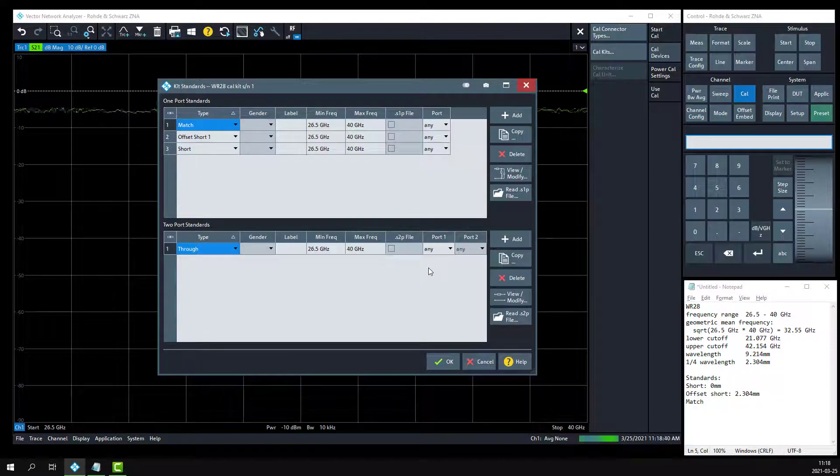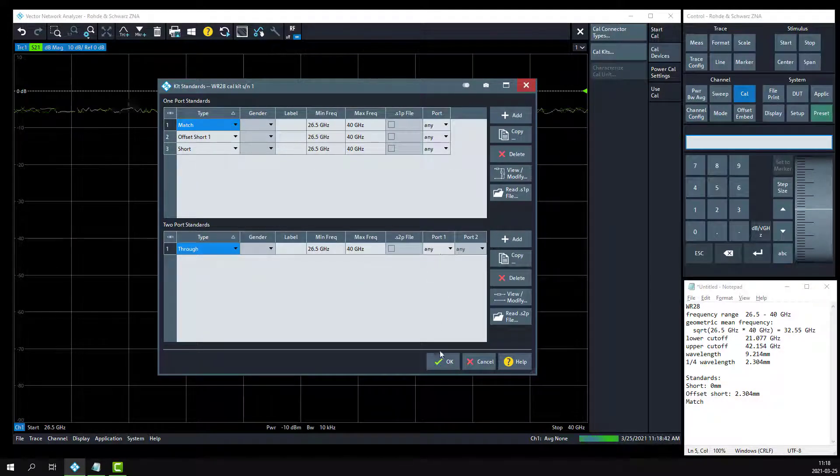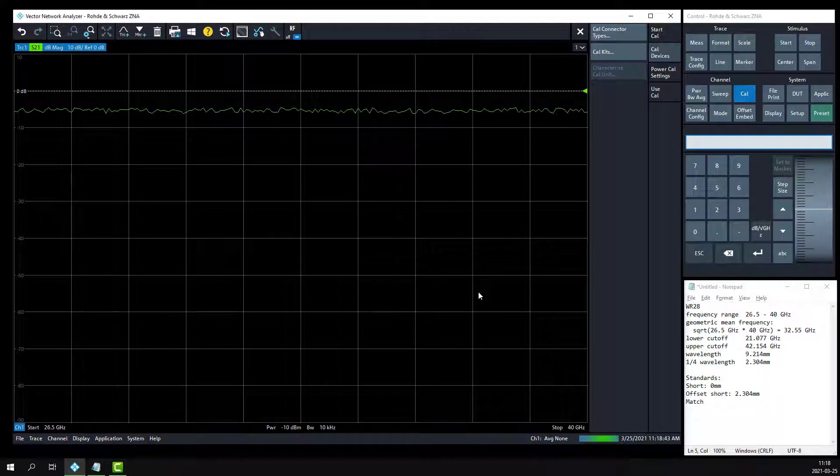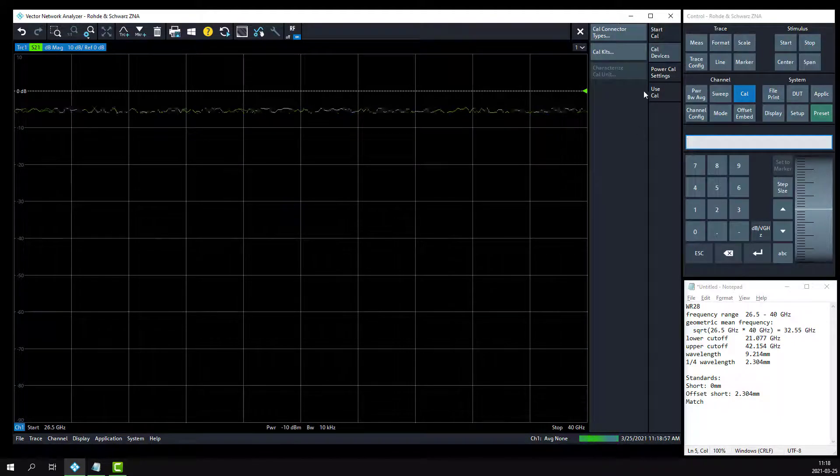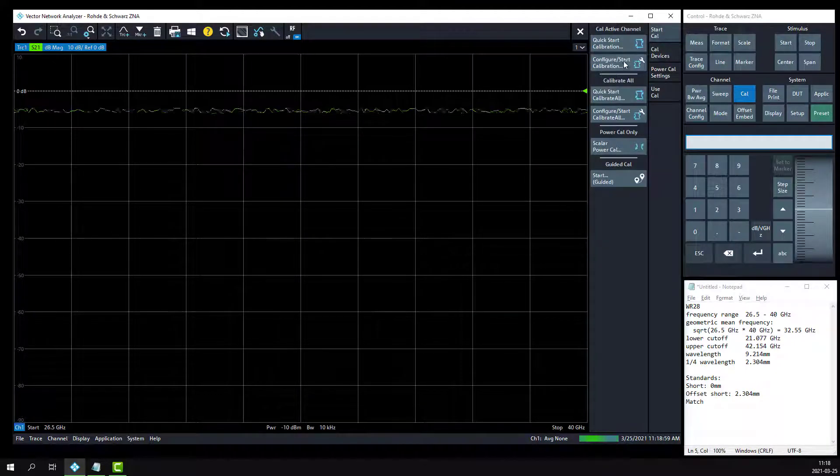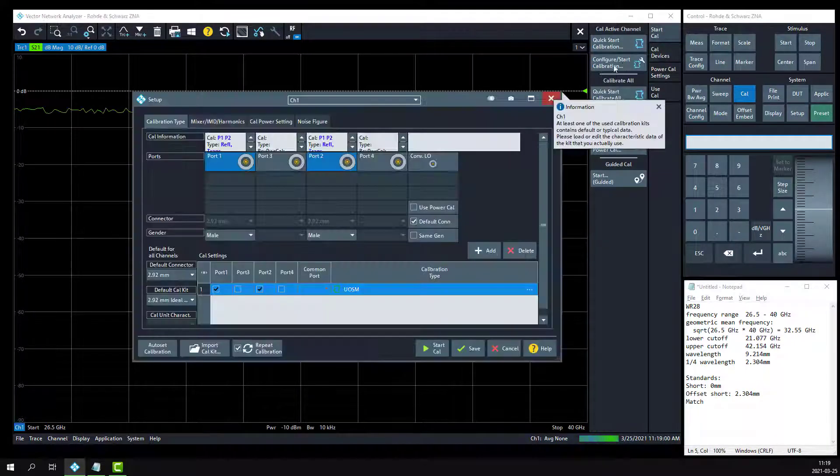We're done defining our calibration kit. Click the OK button. We're ready to make our calibration. Click on the start cal button and go to configure, start calibration.